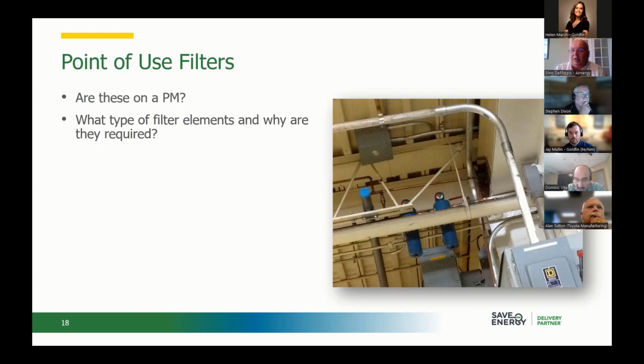There's the problem. Need to make sure that any point of use filters, including FRLs that are actually on the equipment themselves, are on a regular PM, that they're being replaced. Too often, compressors are adjusted in pressure to compensate for something else happening on the demand side that should not be occurring. And I can see where those filters might get less attention than they need to, given their location as well. Now, next slide.